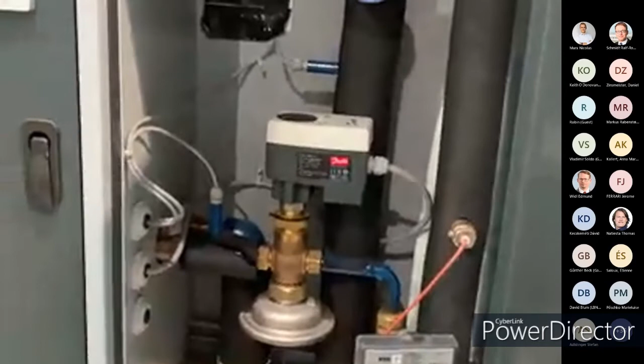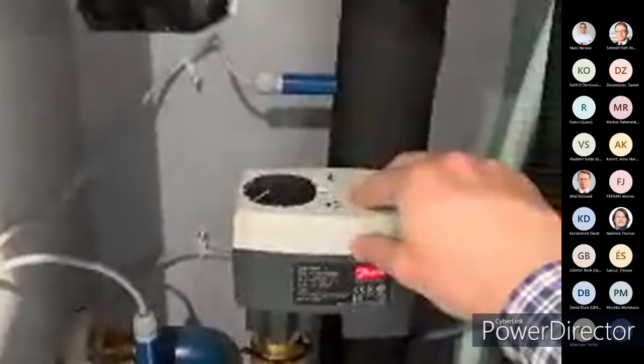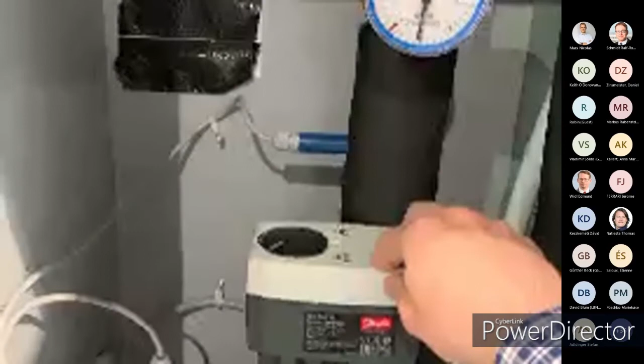Here you can see some of the components, not all. The main component, the heat exchanger, is behind the control panel. We cannot see it, but you can see, for example, the valve which is responsible for controlling the supply temperature, shown as the set point I just mentioned. This valve controls steplessly, and here you can see it's about 3/4 open.